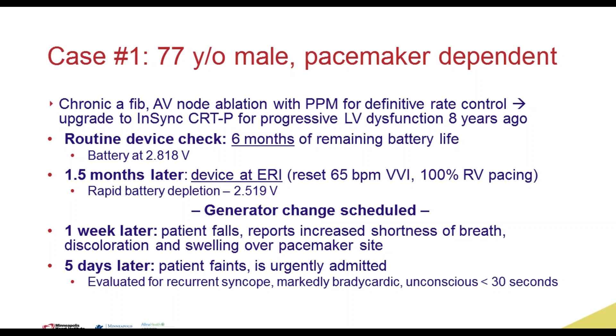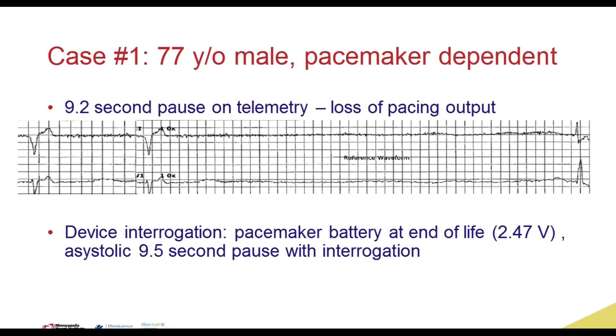And here's just the telemetry tracing. I think, as you can see, there's a 9.2-second pause showing pacemaker failure. There's a loss of output here. There are no pacing spikes, and these beats are not paced, despite this patient having a CRT-P device. And then with device interrogation, the pacemaker battery was found to be at the end of its life, and the patient sustained another asystolic 9.5-second pause with this interrogation.